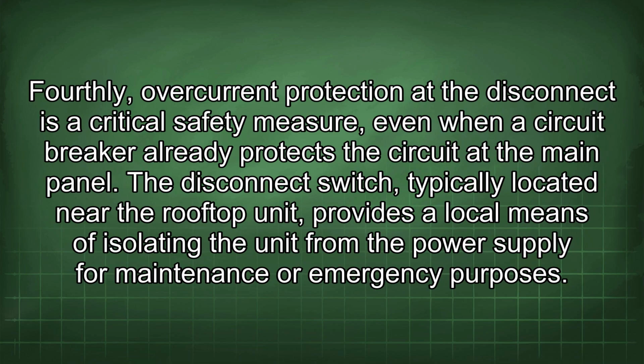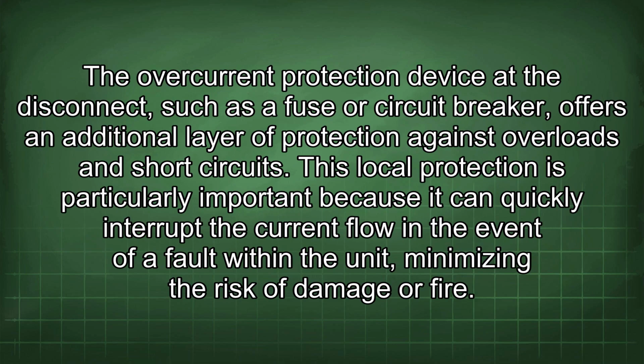Fourthly, overcurrent protection at the disconnect is a critical safety measure, even when a circuit breaker already protects the circuit at the main panel. The disconnect switch, typically located near the rooftop unit, provides a local means of isolating the unit from the power supply for maintenance or emergency purposes. The overcurrent protection device at the disconnect, such as a fuse or circuit breaker, offers an additional layer of protection against overloads and short circuits. This local protection is particularly important because it can quickly interrupt the current flow in the event of a fault within the unit, minimizing the risk of damage or fire.